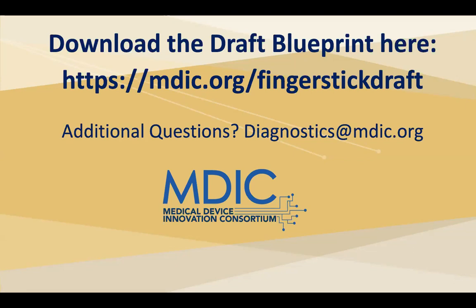Next question. There was mention of using all fingers for studies. Is there a recommendation that CLSI GP42 be followed for collection of capillary blood samples? I would say yes. We are not contradicting any of the existing guidances. Yes. Okay. We didn't specifically recommend it in the document. I don't recall it being specifically recommended in CLSI, but we would have no reason to believe that you shouldn't follow that for the collection of capillary blood specimens. Okay.